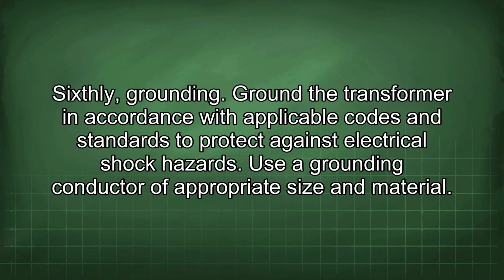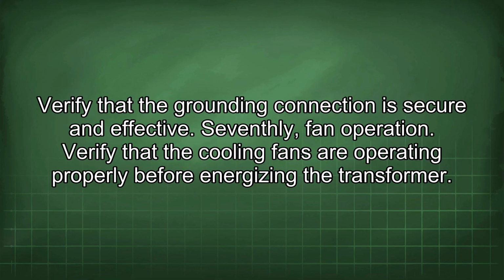Sixthly, grounding. Ground the transformer in accordance with applicable codes and standards to protect against electrical shock hazards. Use a grounding conductor of appropriate size and material. Verify that the grounding connection is secure and effective. Seventhly, fan operation. Verify that the cooling fans are operating properly before energizing the transformer.